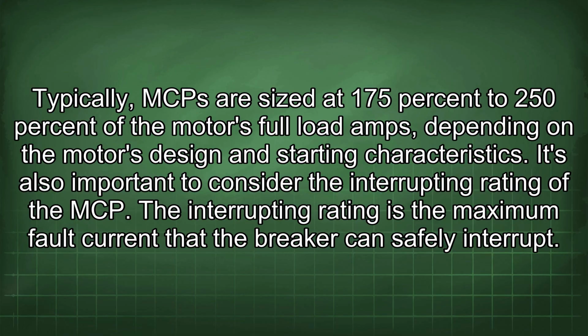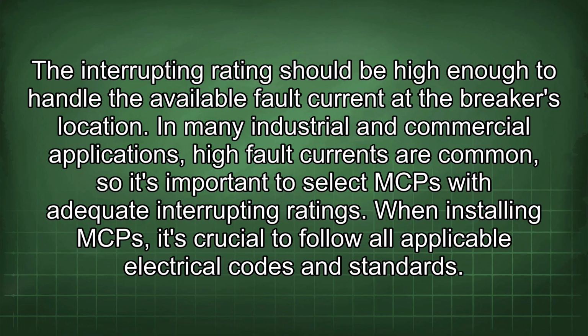It's also important to consider the interrupting rating of the MCP. The interrupting rating is the maximum fault current that the breaker can safely interrupt. The interrupting rating should be high enough to handle the available fault current at the breaker's location. In many industrial and commercial applications, high fault currents are common, so it's important to select MCP with adequate interrupting ratings.